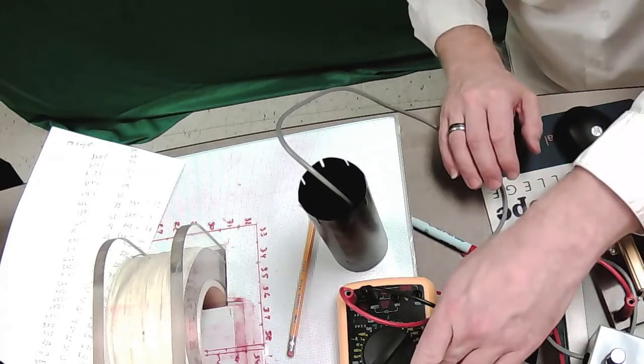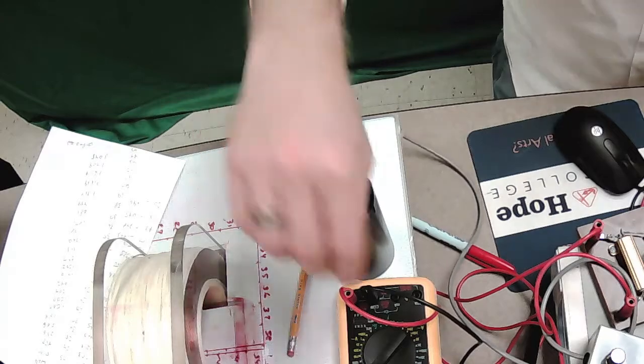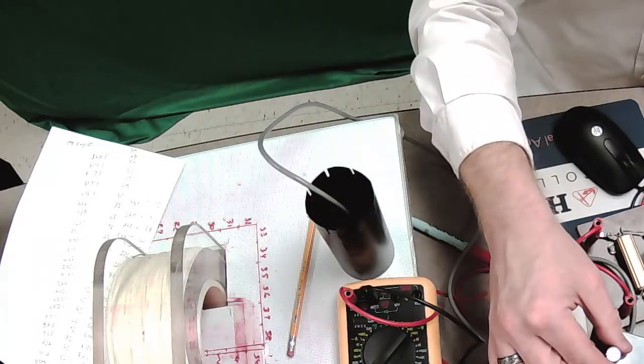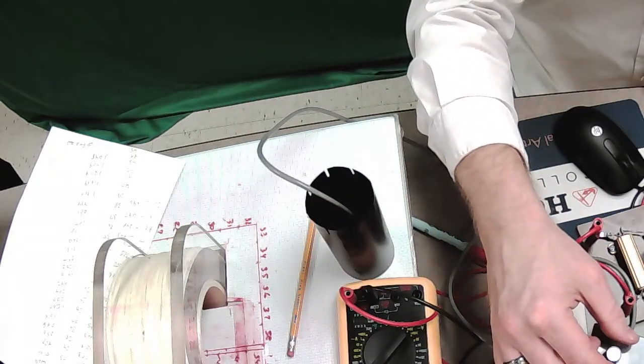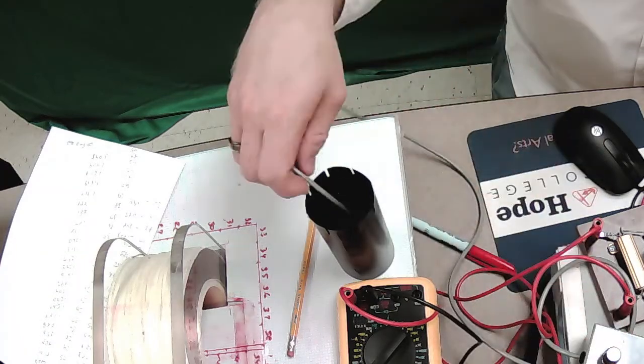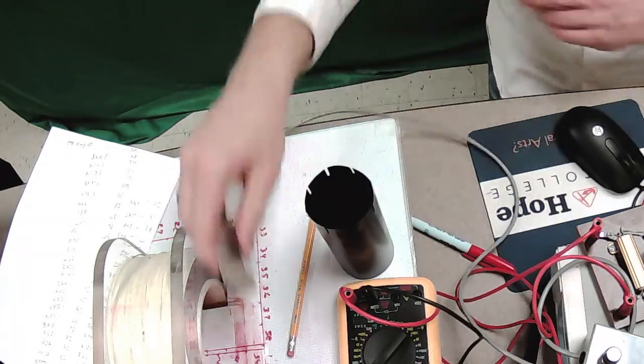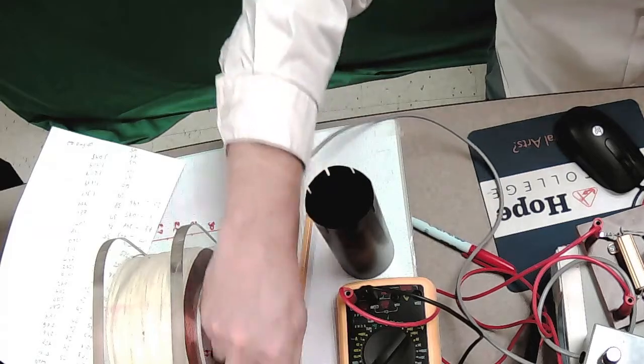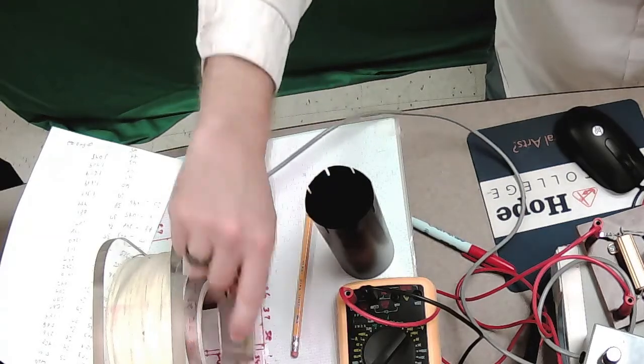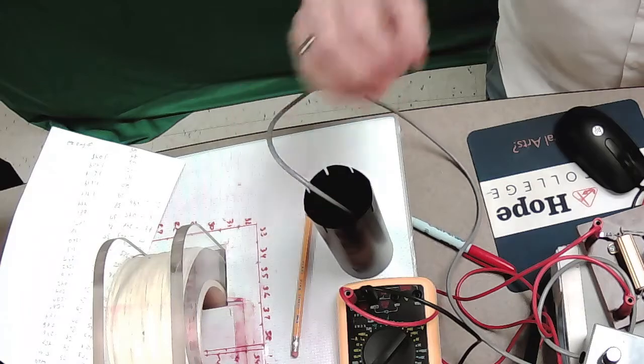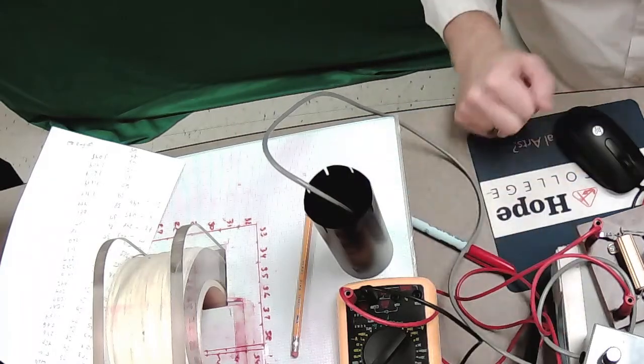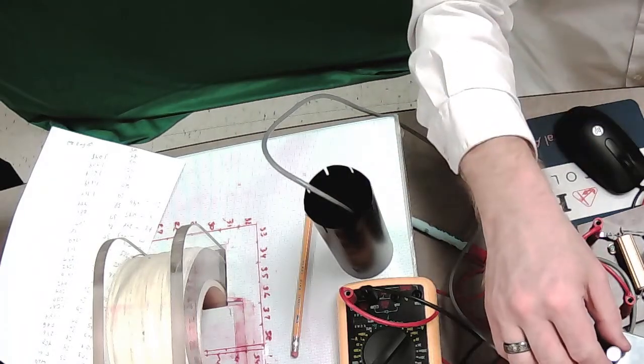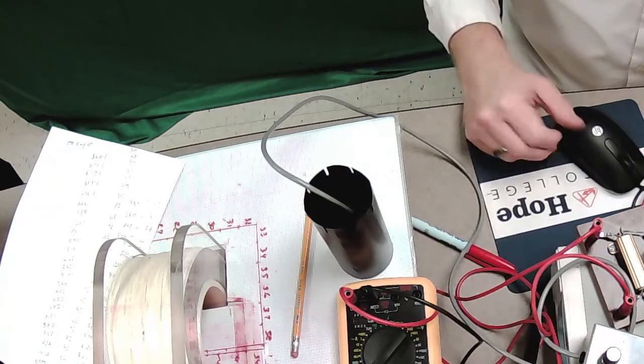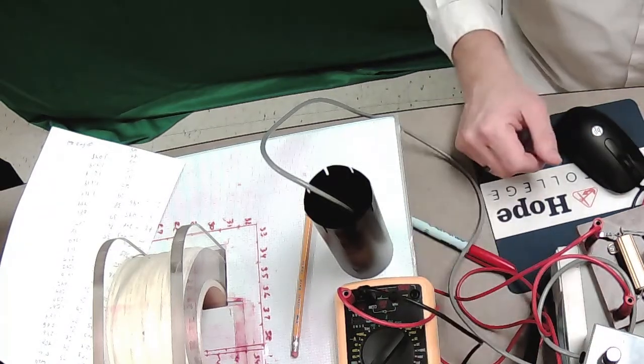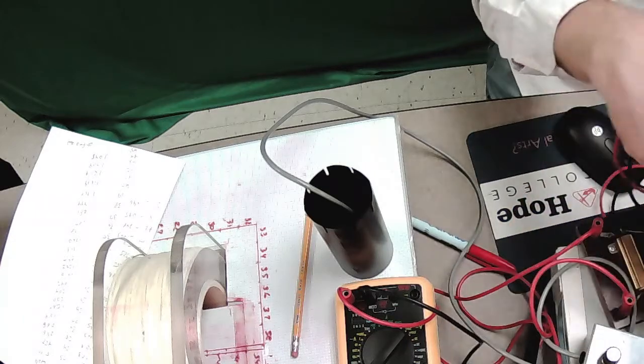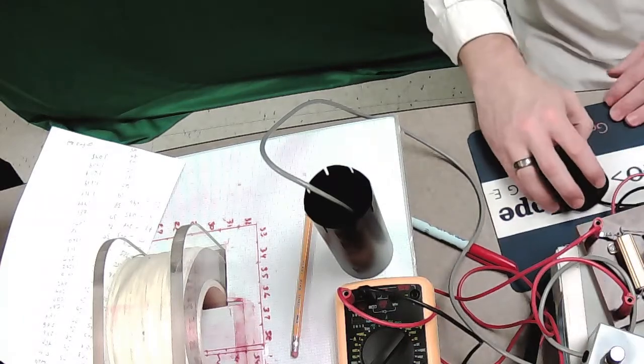Now this other meter, you're going to have to come in and zero this Hall probe a little bit with this gray box. You just turn the knob on the gray box and go back to 0. And through another 5 or 6 measurements, come back and measure again. Notice inside it's really strong. But then you'd come back and put it in, and you would once again keep track of that drift voltage, and then you would also zero it again. I had a drift voltage of about 0.03 here, and over here I had a little bit more drift voltage. And we'll look at that in just a minute.